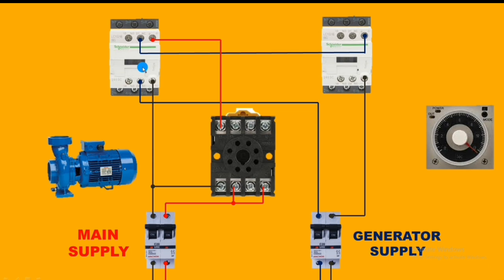If the main power supply comes, first the timer will operate, and after completing the delay time, the main contactor will operate. If the main power supply is cut, the main contactor goes to stop condition and automatically operates the generator power supply — because the generator contactor operates only when the main contactor is in stop condition.